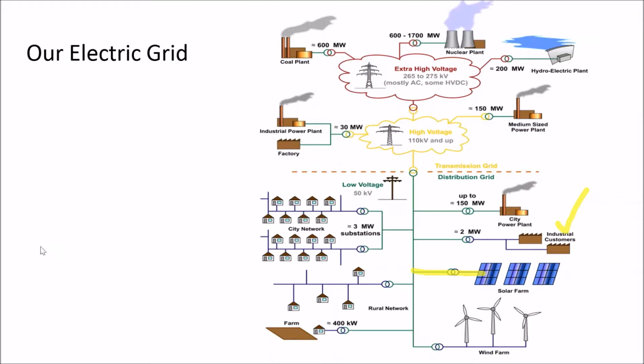Now, on top of that, where the utilities perhaps need to do a better job articulating what happens when solar comes to the grid is at these little distribution nodes where you might hang a transformer right where your electric service is to step down from 50 kilovolts to 240 volts. But then every so often you have other distribution transformers that eventually make it to the substation that steps you up to higher voltage. And the problem with solar is this. If I have a solar farm feeding into the distribution transformer, my solar electricity is going one way, all downstream. My power from my power plant's going downstream, all of my electricity is coming to the load. Well, all of a sudden now we have distributed solar.